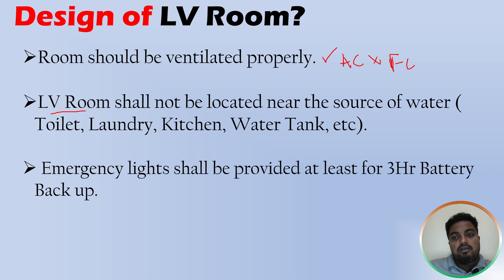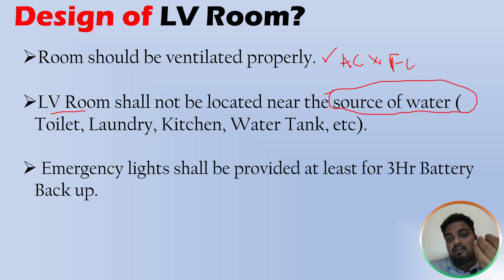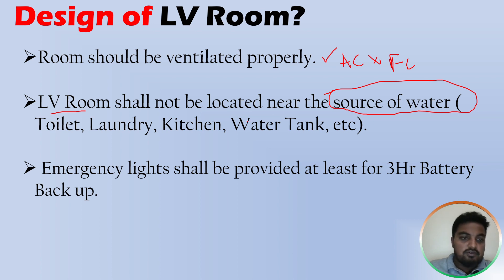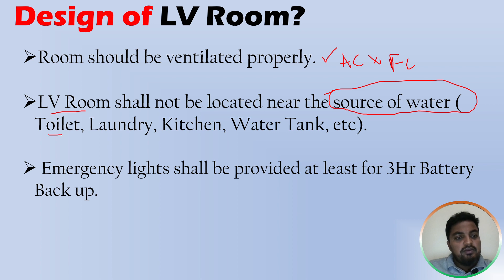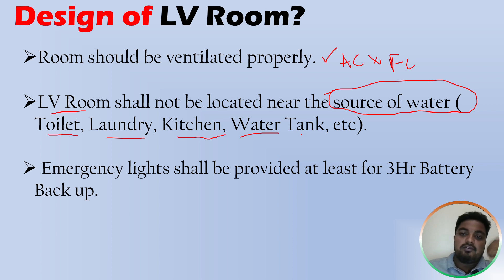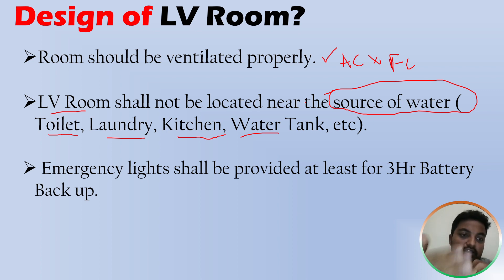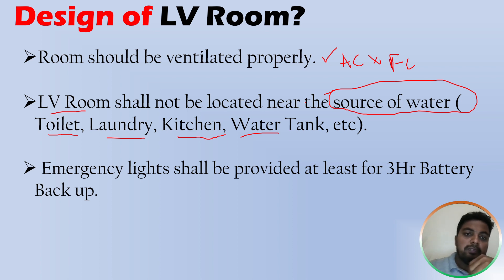The next point: the LV room shall not be located near any source of water. A source of water means any point that supplies water — toilets, laundry, kitchen, water tanks, or water sinks. The LV room should not be designed near any of these. It should be located far away from all sources of water.